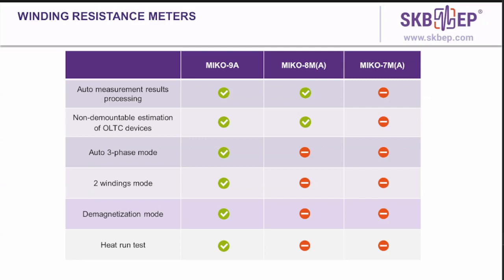Auto three-phase mode. MIKO-9A has additional output for the connection of 2 additional clamps of the crocodile type. As a result, we have simultaneous connection to 3 phases of a transformer and can perform resistance measurement with auto switch between phases. The 2 windings mode. Availability of 4 measurement channels make it possible to implement 2 windings mode, which is used in the transformer of high power capacity in order to reduce the stabilization time on low resistance windings.